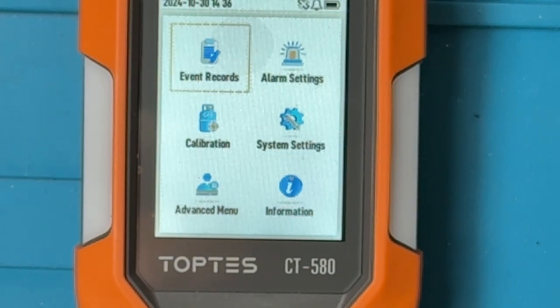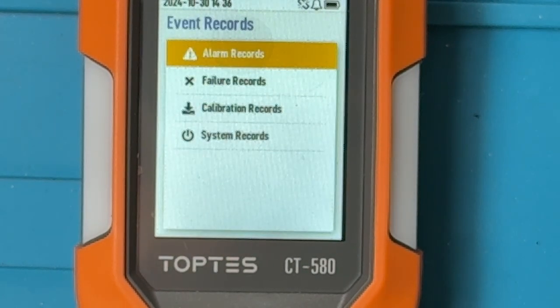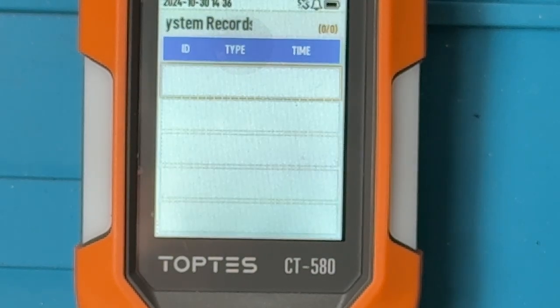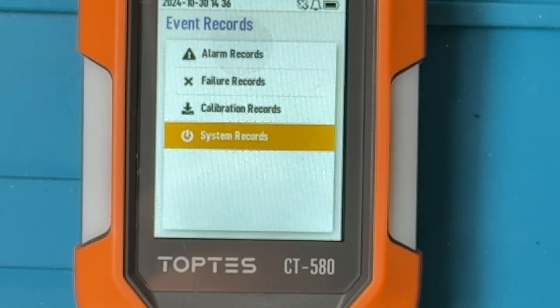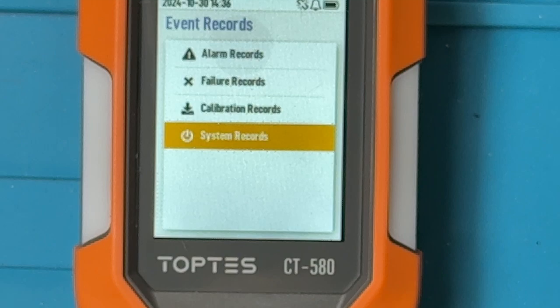And if we look at the event records now, we had some system records, but you can see that those are cleared out now. And so that's a good thing probably to do when you're getting the device ready for use the first time around, as you might have some nuisance records in the unit from when it was set up at the factory.